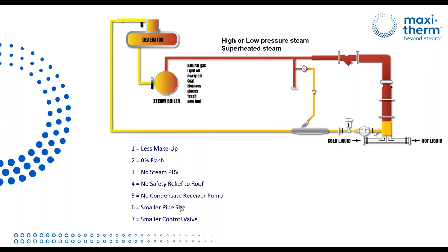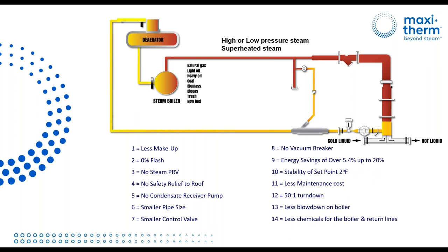Smaller pipe size, because we can use high pressure steam, smaller control valve. Up to a 10 million BTU process, it's a half inch control valve. And again, it's the only moving part. Today we give a 5 year warranty on the control valve. No vacuum breaker. There is a vacuum breaker that's only open when you shut down the system. And there's a huge benefit by not having the vacuum breaker because we don't inject oxygen anymore in the return lines. So less carbonic acid, less amines, less corrosion, obviously.